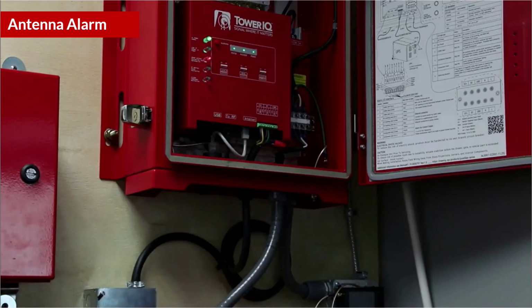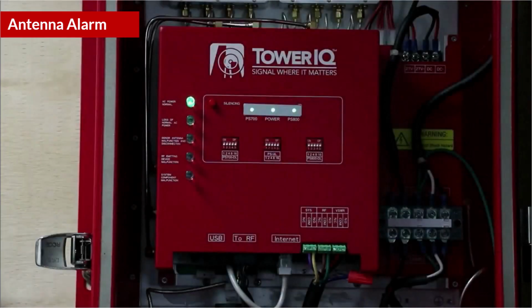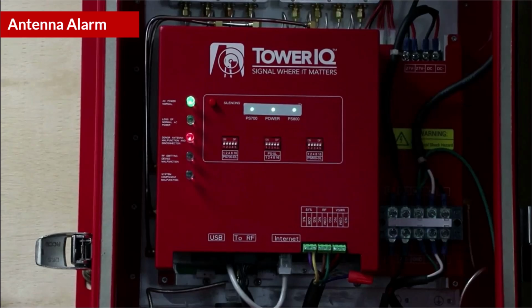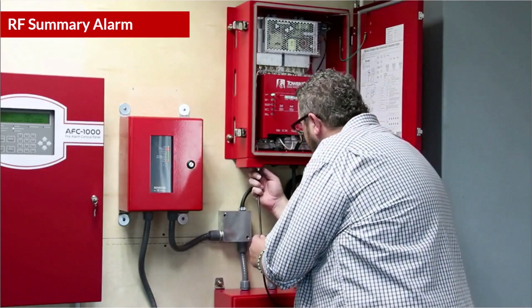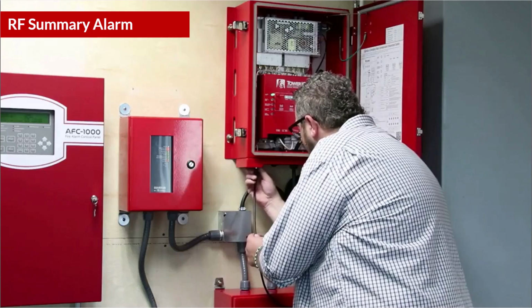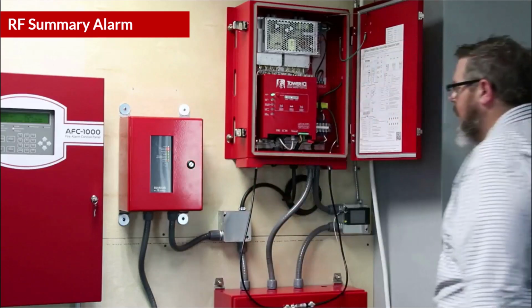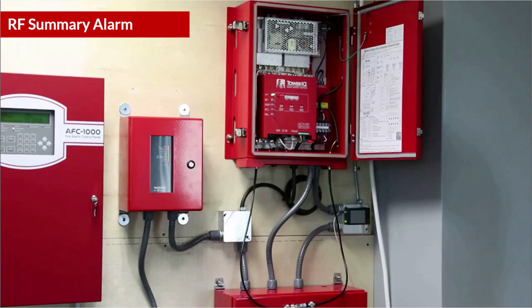The BDA may take a few minutes to activate the VSWR alarm, but once it is triggered, you will see it on both the BDA as well as the annunciator if one is connected. To resolve this alarm, connect the donor cable to the outside port of the BDA. If the cable is properly connected, the visual and audio alarm will cease. The RF summary alarm, or BDA failure alarm, can be activated by creating feedback in the system, putting the BDA into oscillation. In order to not negatively affect the radio network in the area, you should disconnect the outdoor and indoor ports of the BDA.